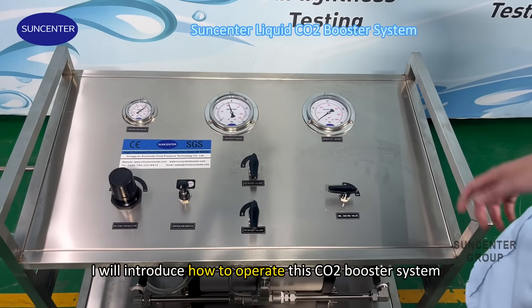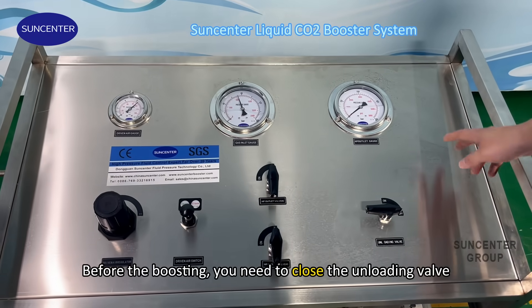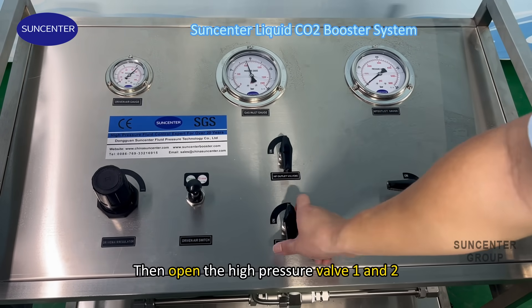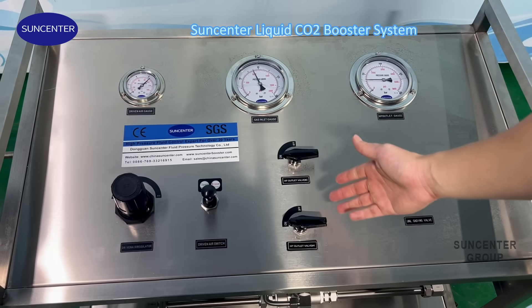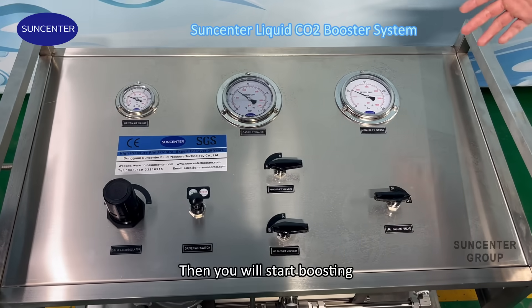I will introduce how to operate this CO2 booster system. Before the boosting, you need to close the unloading valve. And then open the high pressure valve one and two. And then adjust the driven air pressure. And then we can open the driven air switch.